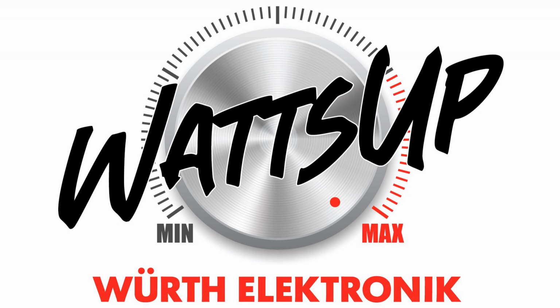So the creepage and clearance distances are met as defined in the UL 60950 for reinforced insulation. So we meet about a working voltage of 265 VRMS and overvoltage category 2 and the pollution degree 2 environment. Yeah, next week we'll look into the losses.